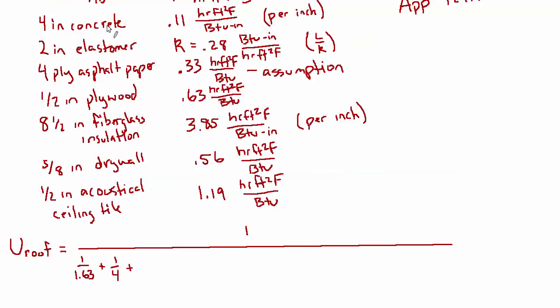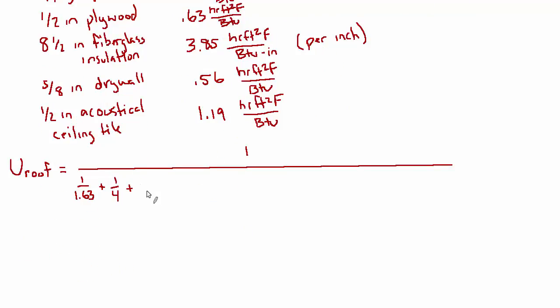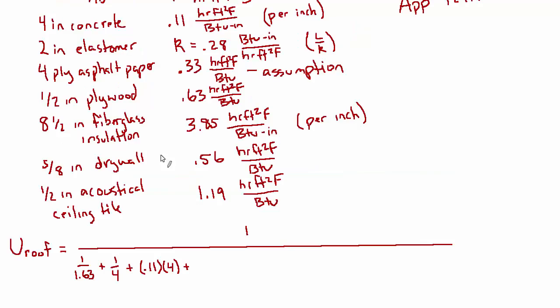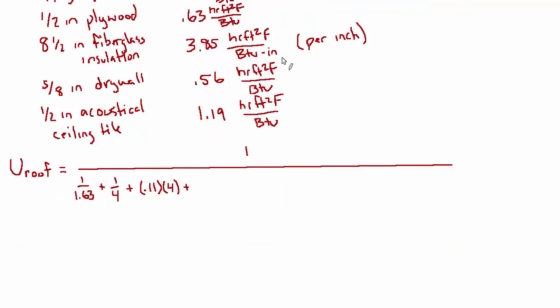And the next one we had was the concrete, which is on a per inch basis, and it's 4 inches of concrete. So 0.11 units of resistance per inch times 4 inches. And then next we have this elastomer where they gave us the K value, so this is going to be an L over K situation. It's 2 inches, so 2 inches over 0.28 plus 0.33, which is our assumption for this asphalt paper. And then 0.63 for the plywood, and then 3.85 times 8.5 inches for the fiberglass insulation, 0.56 for the drywall, and 1.19 for the acoustical ceiling tile.